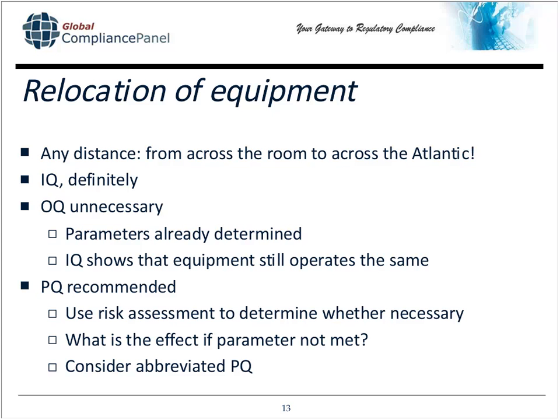I've seen firms perform abbreviated PQs by saying this instrument has just been relocated a short distance. It was put on a truck at one location and taken off a truck at another location, and that the IQ addresses things. However, to go over and above, they're going to perform an abbreviated PQ. Anecdotally, since I've never done this, my acquaintances in the industry have told me that what happens here is that the regulatory inspector asks a lot of questions. Well, I understand, what made you do an abbreviated PQ? And there's a lot of rationalization and justification that goes on.